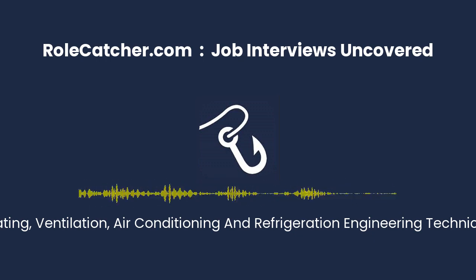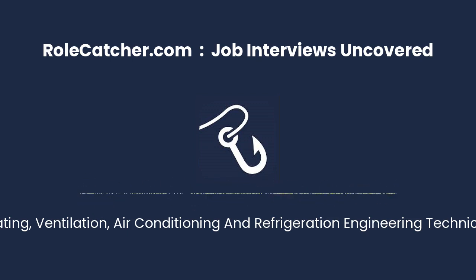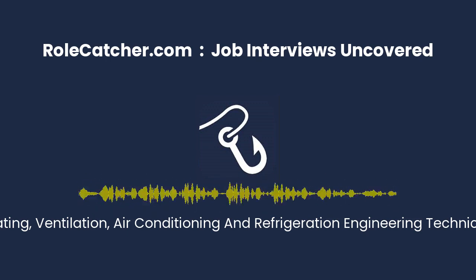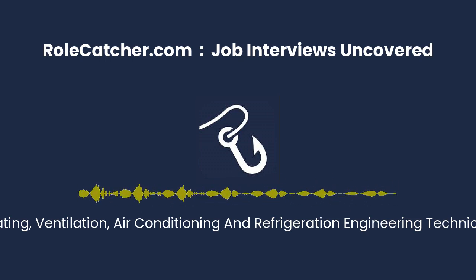So to test my theory, I carefully bypassed the high-pressure cutoff switch, and I kept a close eye on the system. And just as I suspected, the cooling problem disappeared. So it was the switch all along. It was the switch. Right. So I replaced the faulty switch with a new one, and I made sure it was wired correctly and everything. And then we ran the system through a series of tests, and everything checked out. The cooling problem was gone.